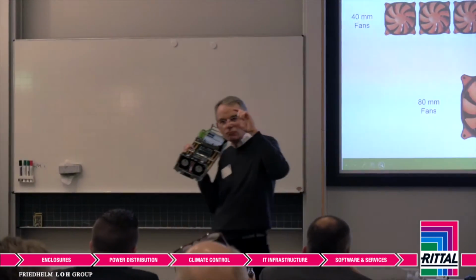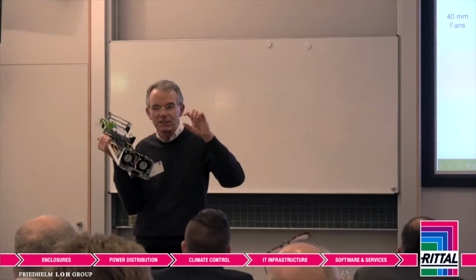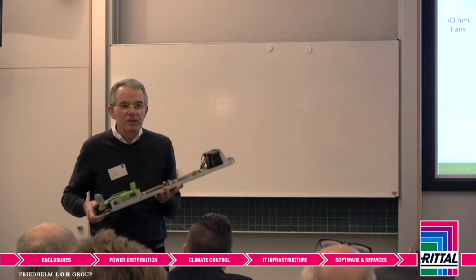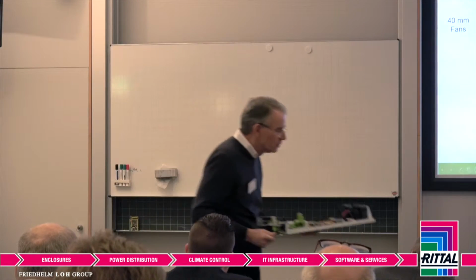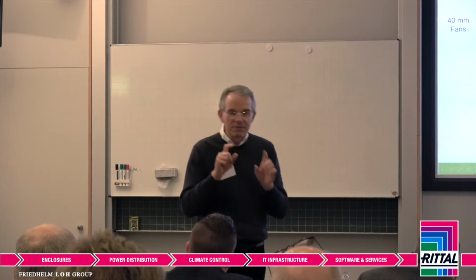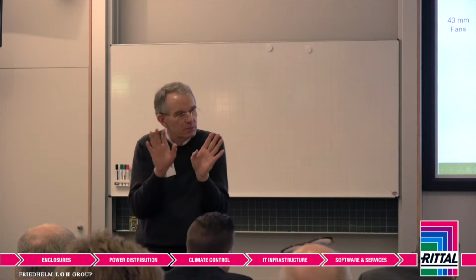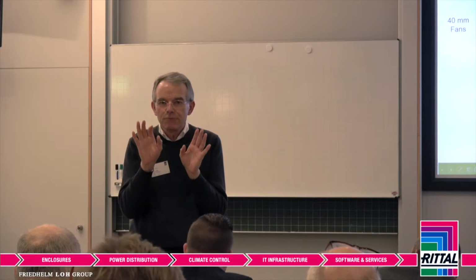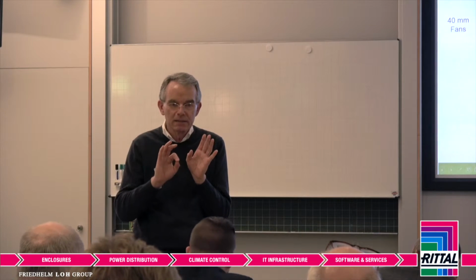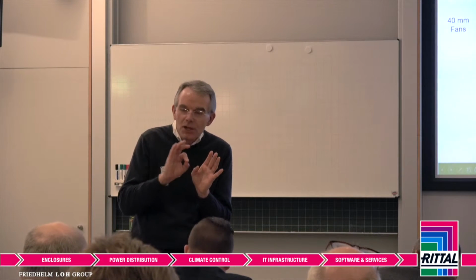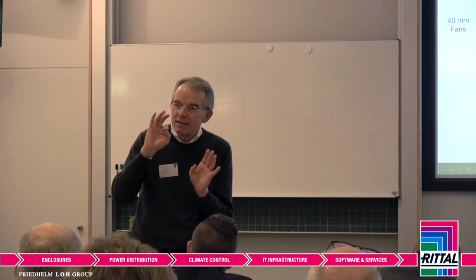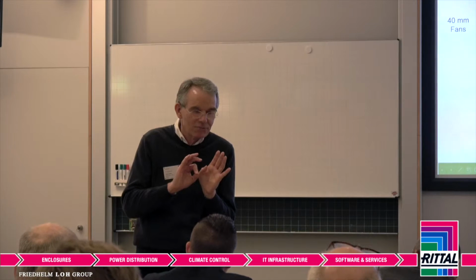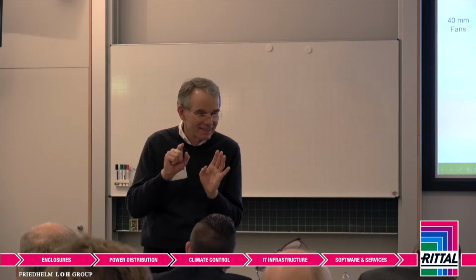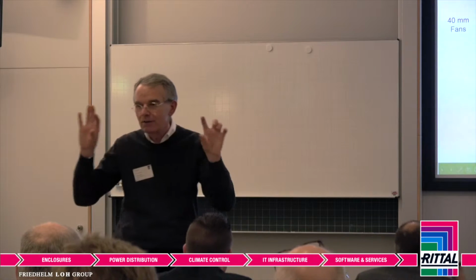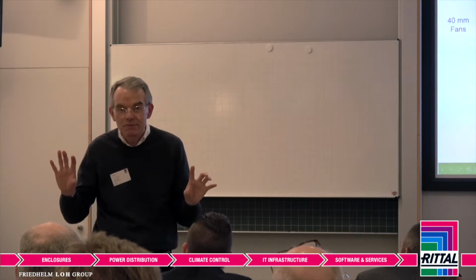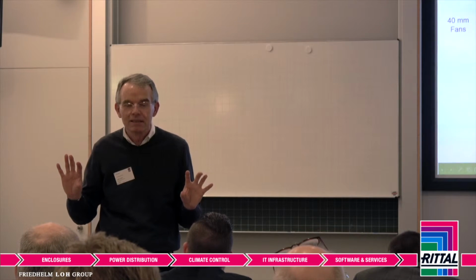So inside a rack unit for an open rack, it's actually taller. If anybody knows the cube law, it's called the fan cube law - it's basic physics. The cube law is this: if you reduce the speed of a fan by half, you reduce the power down to 1/8. So if you use big fans that spin slower, you massively reduce the power. So the fan power in an OCP server is about 1/10 of a conventional server.